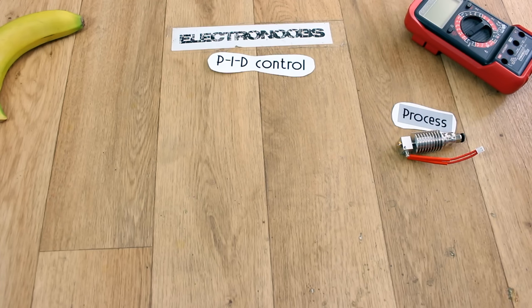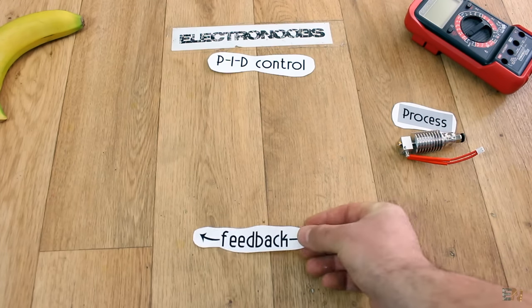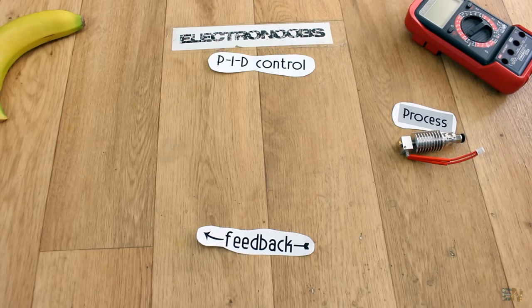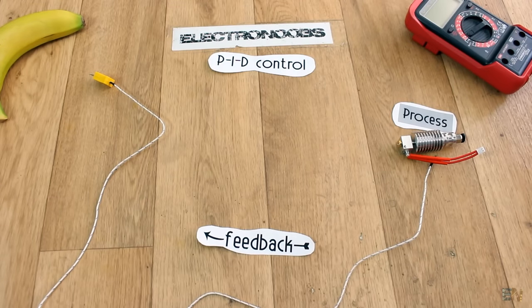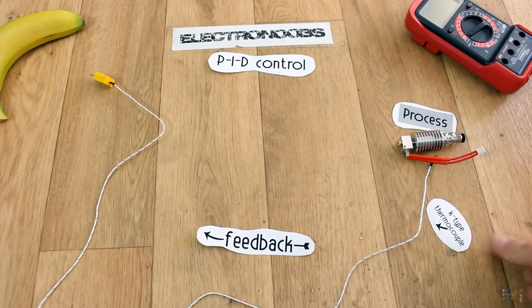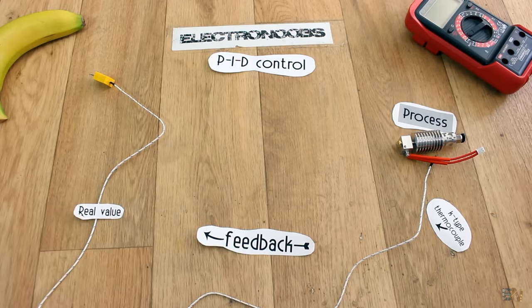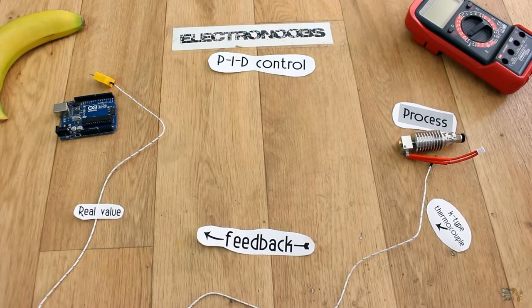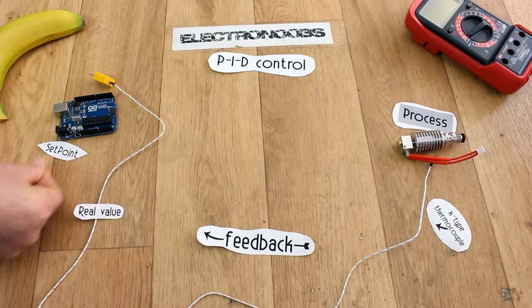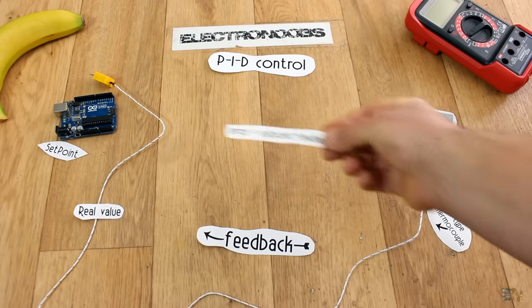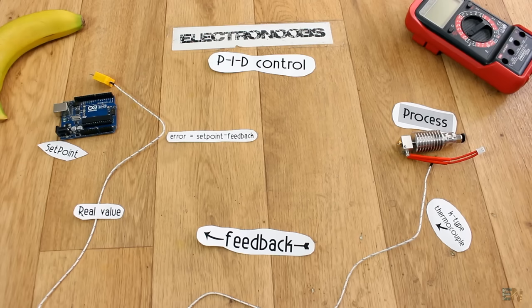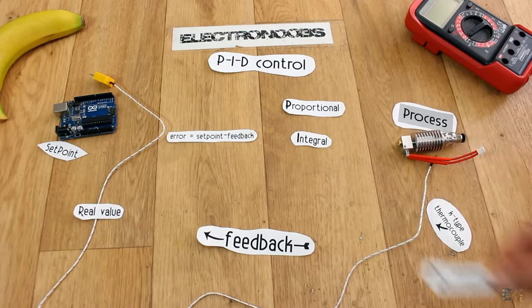In order to control this temperature, we will need a feedback. So, any PID control will have some sort of feedback. In our case, that feedback is made using a K-type thermocouple that will measure the real temperature of the system. This type of control will also need a set point, which in our case is the desired temperature. The system will make the difference between the desired value and the feedback from the output. And using three constants, the proportional, the integral and derivative, we can change the output according to the feedback.